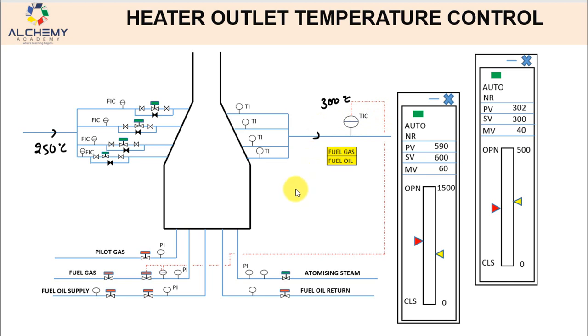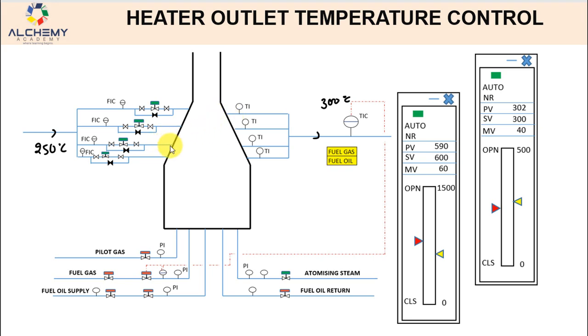Through the controller — meaning through a firing heater. How does the heater operate? Basically there is direct firing into the heater; burners will be there that burn, fired by fuel gas or fuel oil supply. Heat transfer to the process fluid happens by radiation and convection. Tubes in the radiation section get about two-thirds of the heat transfer, and coils in the convection zone get the remaining one-third. This control philosophy — including cascade control — is what I will discuss in this video lesson.